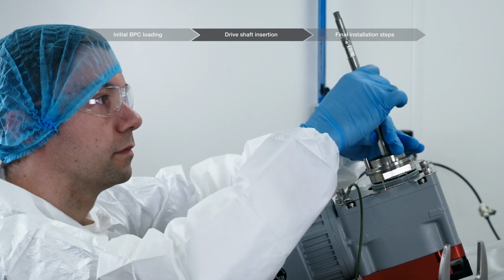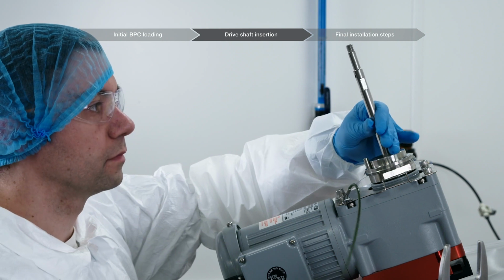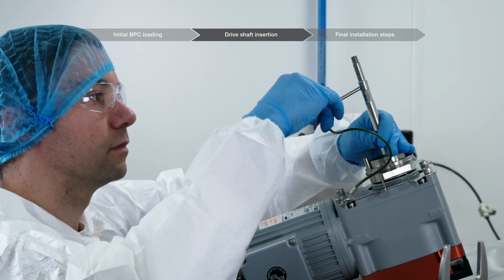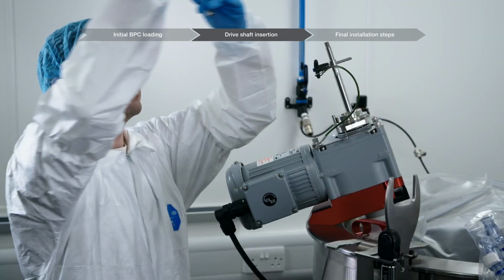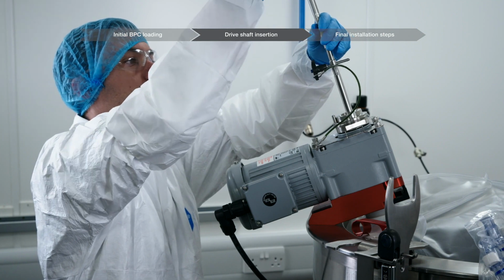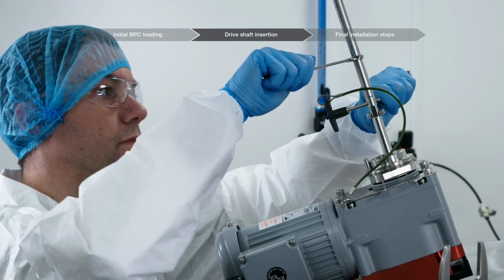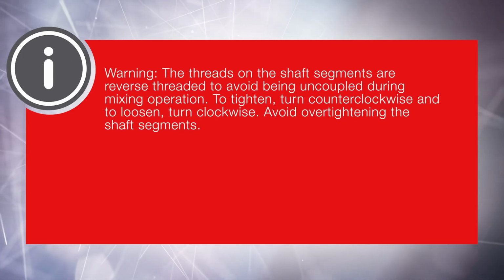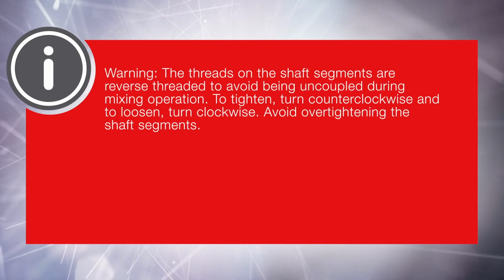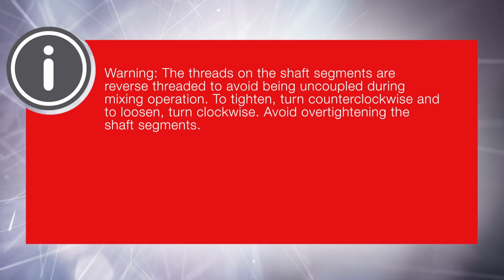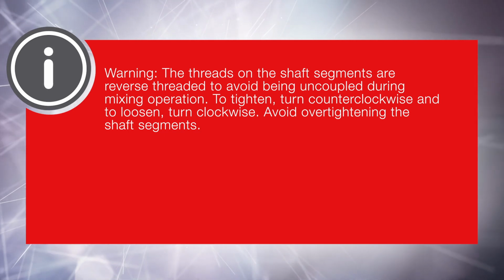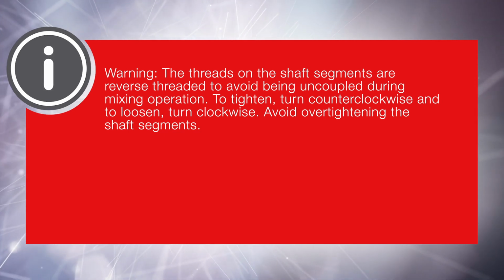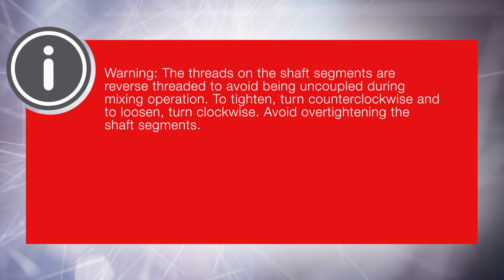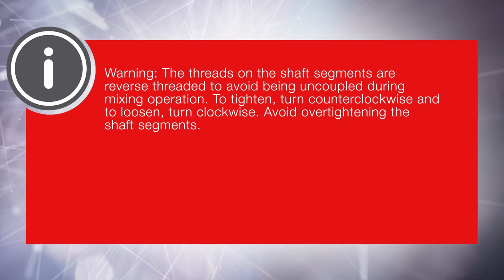If applicable, first assemble the drive shaft. Insert the first piece into the motor and hold it in place with the pin. Attach the second piece. You may optionally use the supplied ring wrenches to tighten. Warning: the threads on the shaft segment are reverse threaded to avoid being uncoupled during mixing operation. To tighten, turn counterclockwise, and to loosen, turn clockwise. Avoid over-tightening the shaft segments.